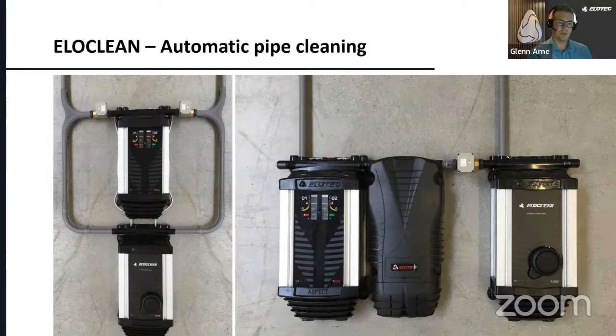We also have something called the EloClean, an automatic pipe cleaning system. This could be a good addition where there are extreme amounts of dust and dirt inside the pipes, or if it's difficult to get access for cleaning. It does this automatically, and can be adjusted to run once a week, once every second day, or once a day. It has a function that closes the inlet to the Elotec Aspect and blows outside the pipe, so air doesn't come inside the Elotec Aspect, only through the pipeline. This can be a good addition, so you know it's possible, but remember it's not needed in every installation. It's for when the environment is harsh, or when it's too difficult to clean the pipes—then you may need this one.